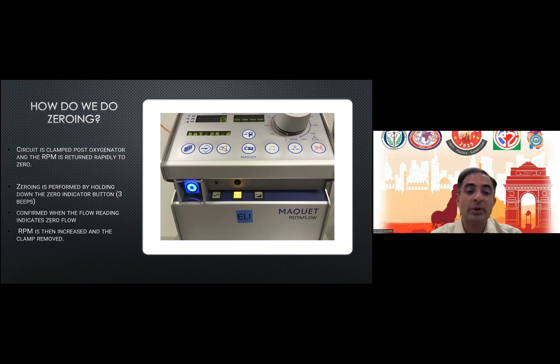Once the initial settings of the console are done, the ECMO is ready to go, and once the operator who has inserted the cannulas is ready, you ensure that optimal connections are done. When we start the ECMO, choose the ECMO settings to the lowest, about 1500 is what we start with. The usual recommendation is to start the initial oxygen flow equal to the blood flow, so there is no rapid reduction of the CO2 resulting in alkalosis or other acid-base disorders.